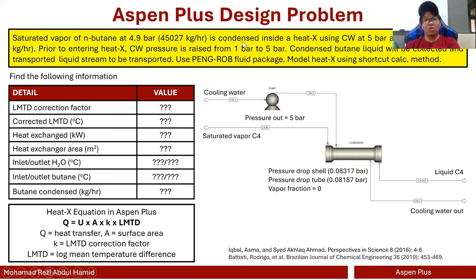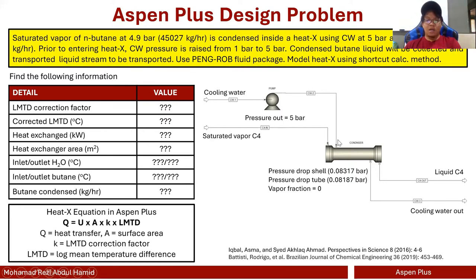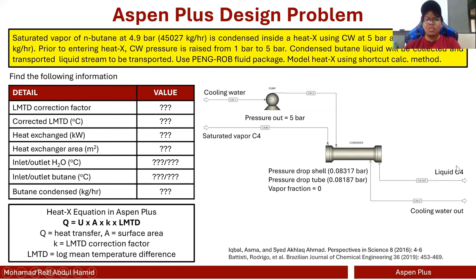For our design problem today, we're going to focus on the condensation of n-butane. We have n-butane coming in as a saturated vapor at 4.9 bar, with a flow rate of 45,027 kg/hr. It will be condensed using cooling water coming in at one bar, which will be raised to five bar before entering the heat exchanger. What comes out will be slightly higher temperature cooling water as well as liquid butane. We're going to try to condense all of the incoming butane.